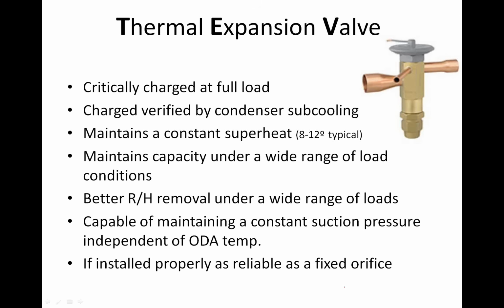If the total superheat is too high on a TXV system, the solution is not to adjust the TXV to get the evaporator superheat lower and the total superheat lower. What you really have to do is insulate that suction line better so that it doesn't pick up as much heat between the time it leaves the evaporator and the time it enters the compressor, right? That's really an insulation problem. You've got to have that line better insulated.